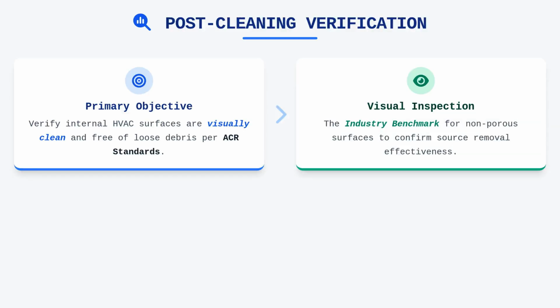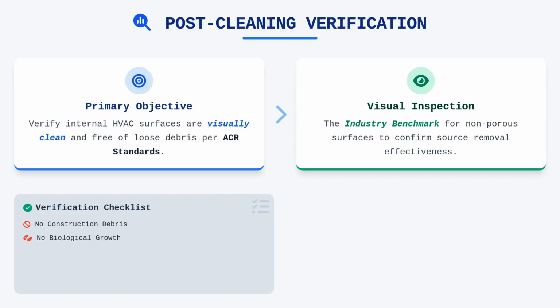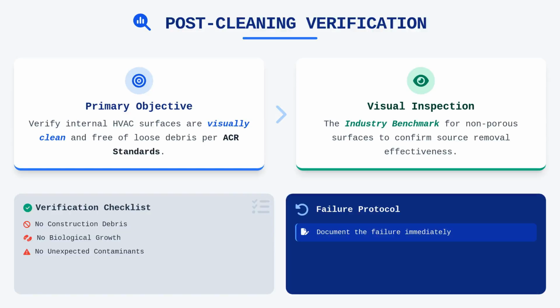We rely heavily on the visual inspection method for non-porous surfaces, which serves as the industry benchmark for confirming that our source removal techniques were effective. When you perform a visual inspection, you are looking for more than just a lack of visible dust. You are checking for an absence of construction debris, biological growth, or unexpected contaminants that survive the cleaning process. If any area fails to meet these criteria, it is your responsibility to document the failure and immediately perform re-cleaning of that section until the standard is satisfied. Always remember that the burden of proof lies with the service provider to demonstrate that the system meets the established cleanliness benchmarks before closing out the project.